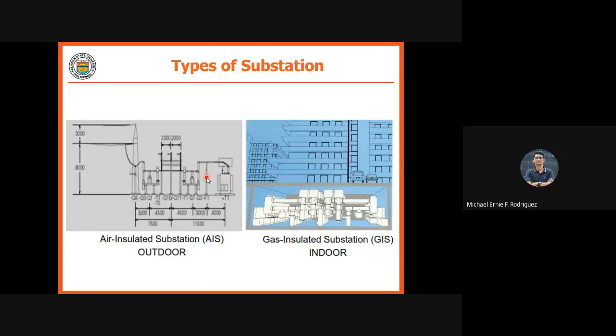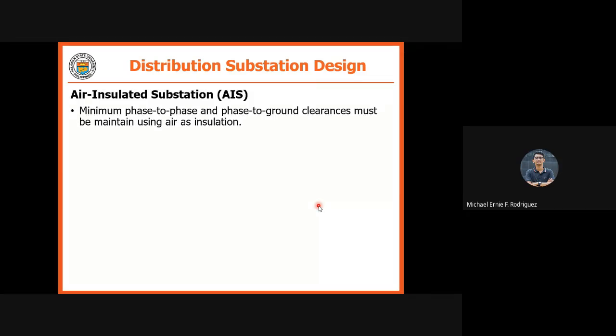Okay, further, AIS on the left and GIS on the right. This one, usually GIS, is placed underground, the GIS in the figure is underground. This one, of course, is above the ground, and the insulation is air. This one is gas. So AIS, or air insulated substation, has minimum phase-to-phase and phase-to-ground clearances to follow. When you have air insulation, we need to maintain the minimum phase-to-phase or phase-to-ground clearances. Why? If we cannot maintain this minimum, we may have electrical arcing, which will lead to short circuit and can cause failure of your equipment or, in the worst case, of your substation.